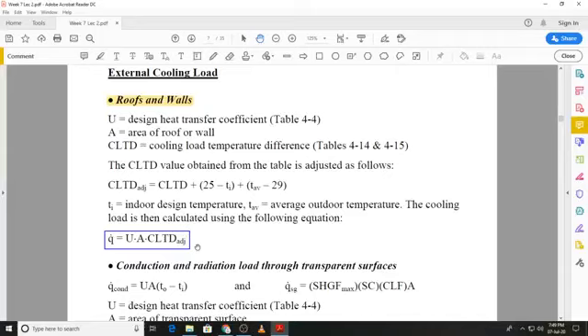So for a particular roof or a wall, the U value will be given to us, or we can find it ourselves if we know the construction of that particular roof or wall. A will be the surface area through which heat transfer takes place. That can also be obtained from the plans of the building. Then the CLTD value will be obtained from a table, but that CLTD value given in the table is for a particular set of inside temperature and an average outside temperature. But it is not necessary that our design temperature inside the conditioned space and the average temperature where we are calculating the cooling load are the same as the reference values in the table.